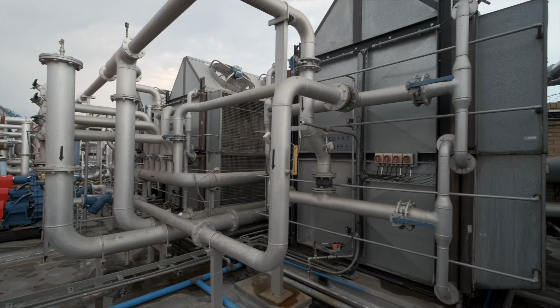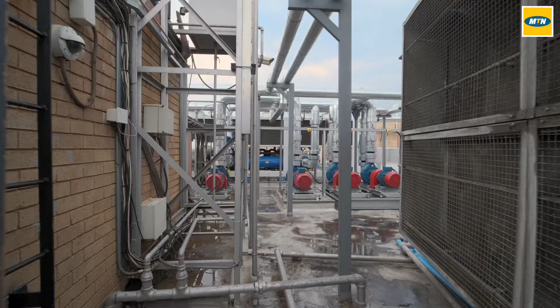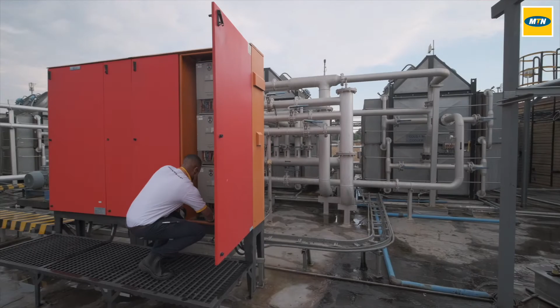These are multiple distribution paths, which allow for concurrent maintenance. You have multiple cooling towers per colocant. At any stage, one can be switched off for maintenance reasons while the others keep the plant operational.